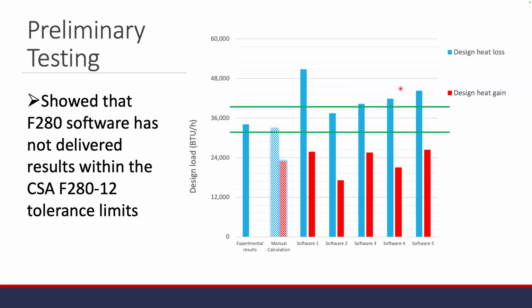But the flip side is 4 of the 5 were above the 20% threshold, overestimating the heat loss by more than 20%. If you were to go buy the next furnace size up from that number, there's a very good chance you bought a furnace bigger than it needed to be, because the software is already 20% inaccurate, and if you're a conservative person, you like to buy 20% over the number your software generated. So we could now be quite a bit bigger than necessary. 4 of the 5 softwares at this preliminary stage were overcalculated, one of them quite substantially.